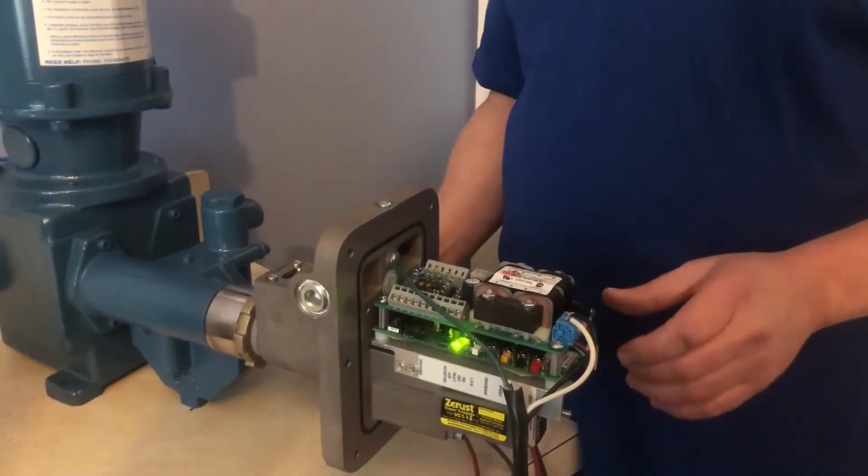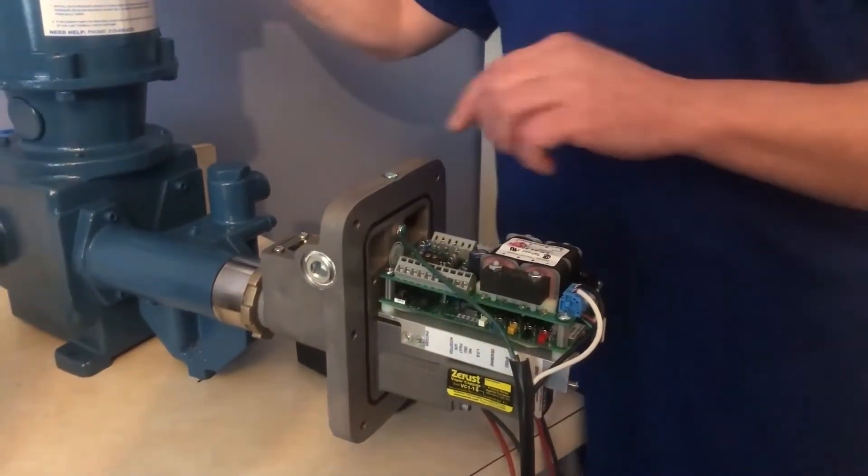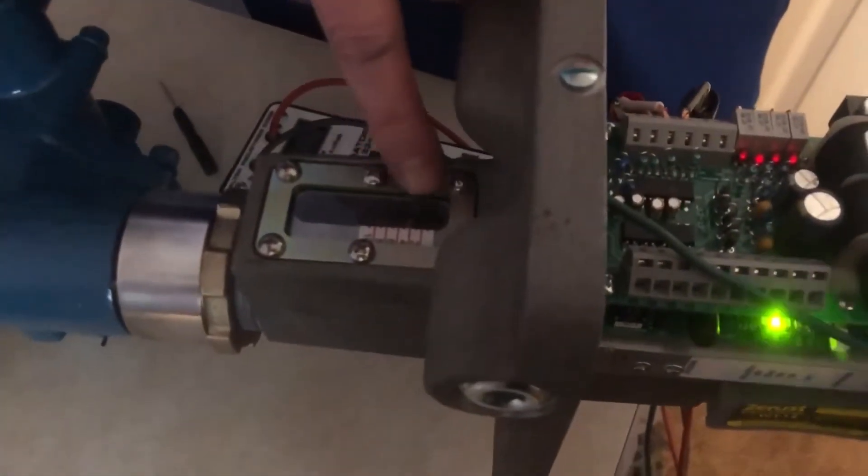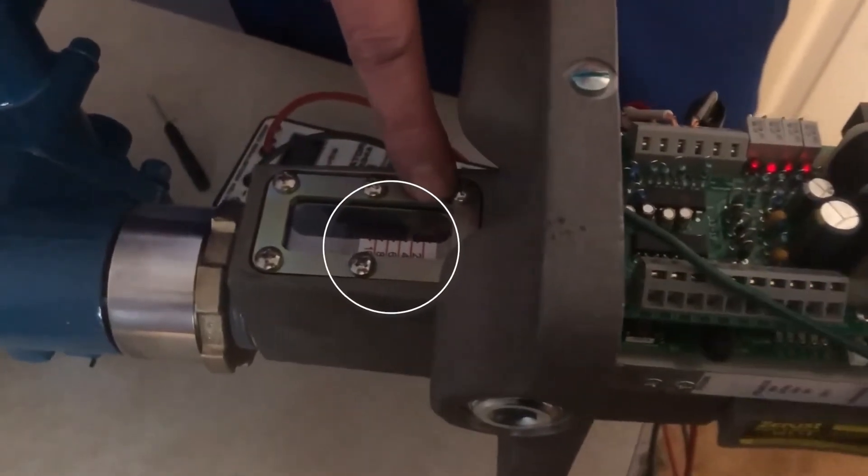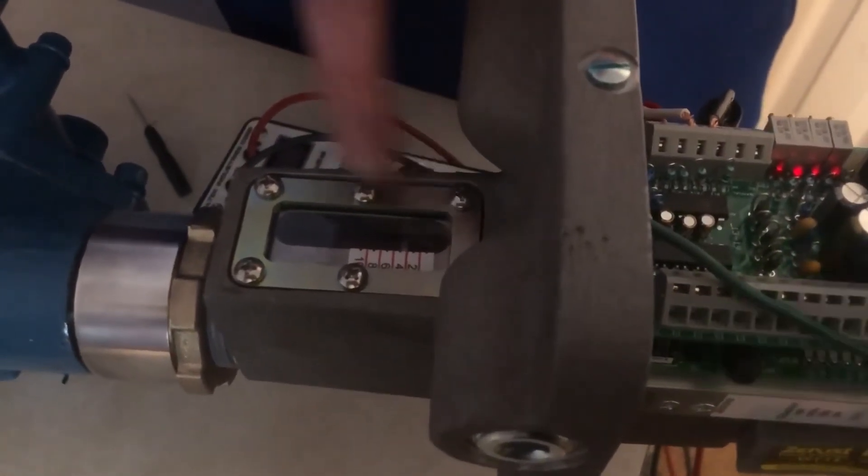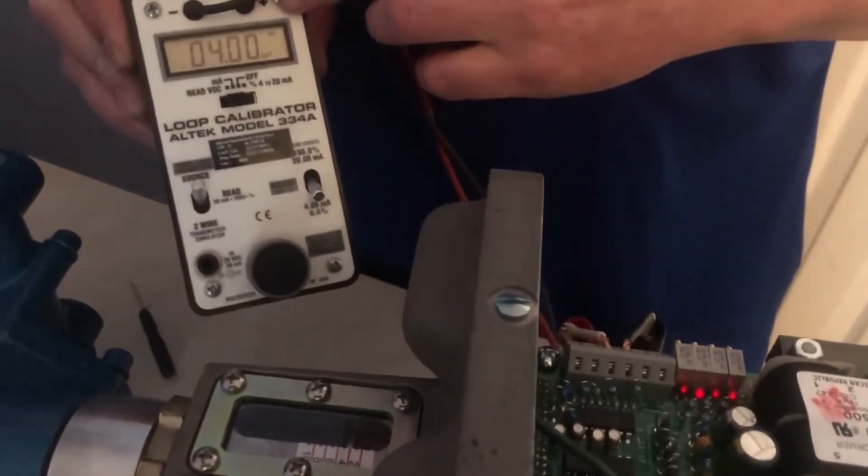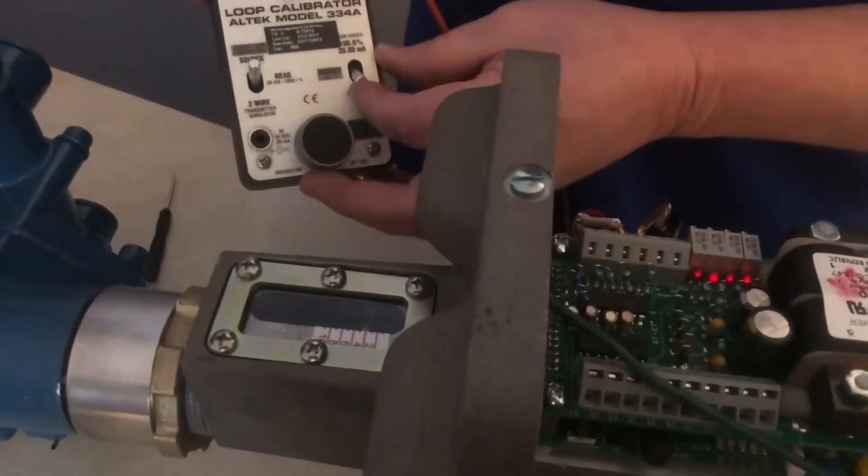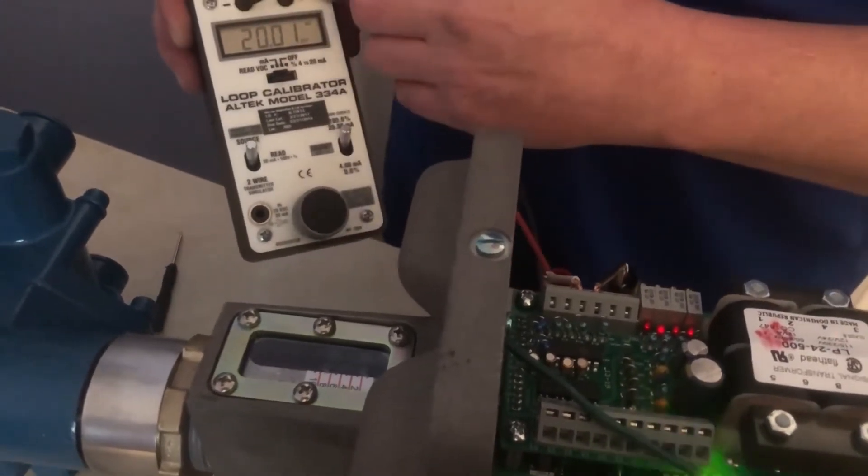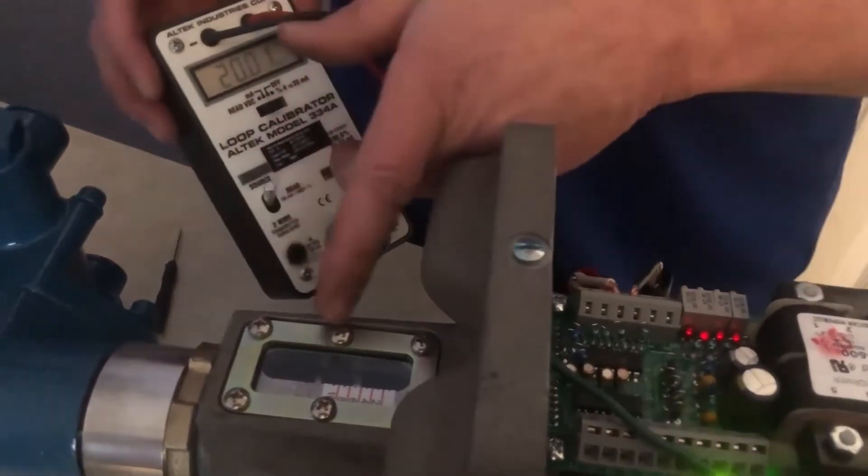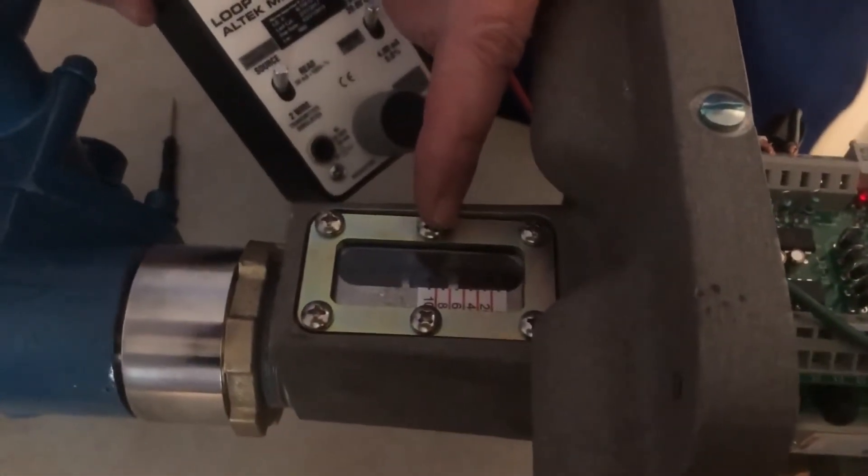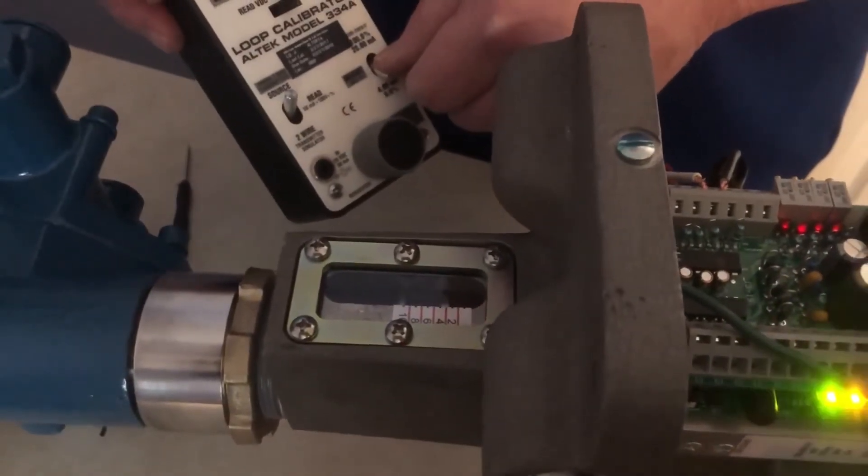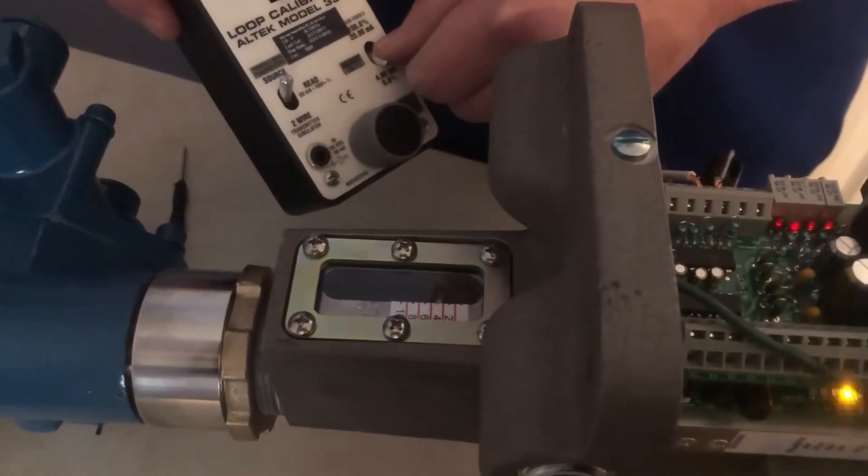Now, four milliamp from the factory is zero stroke on the pump. And if you come over here, you'll see that we have our scale here from zero to 100. And you see that little white spot that indicates zero stroke or the four milliamps that we're simulating into the controller. Now, I will adjust the simulator to 20 milliamps. And you see that the stroke has gone up to 100%. So again, 20 milliamps being 100 and four milliamps being zero stroke.